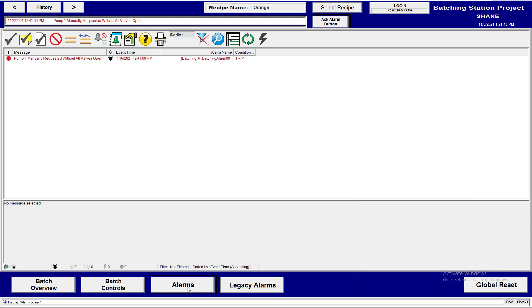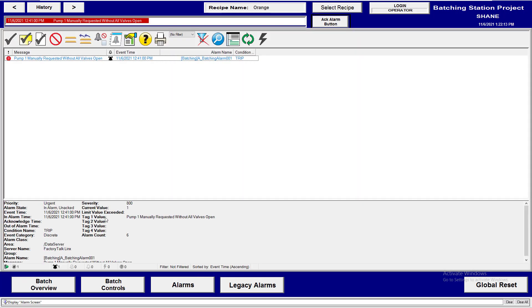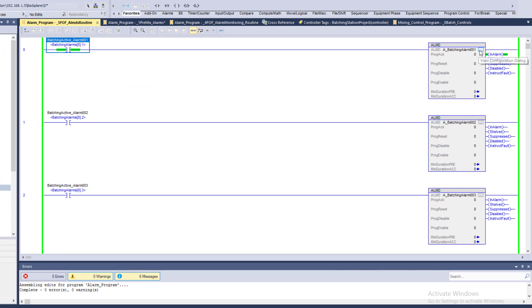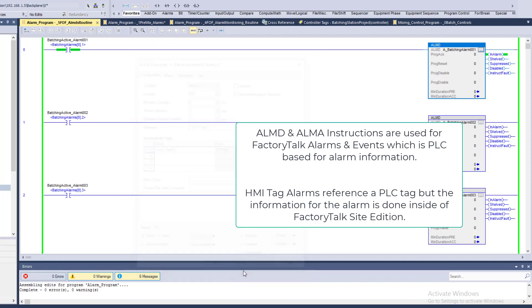Currently I have an alarm on Alarms and Events showing up — this is from the batching station project I've made on YouTube. I also did the servo project, and it has Alarms and Events as well. This is the Alarms and Events screen — it gives you all the information from the ALMD. The ALMD is inside the PLC processor and is a digital alarm instruction. You set it up in your processor to give you a message via a tag in simple ladder. If the ladder rung is true, the instruction triggers and displays the message, and you can also reset it.